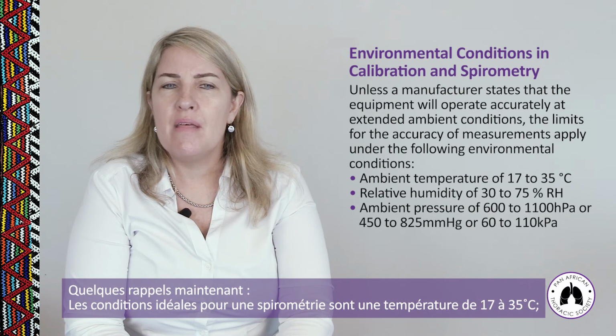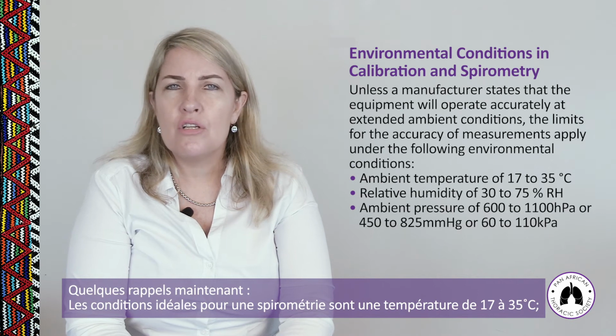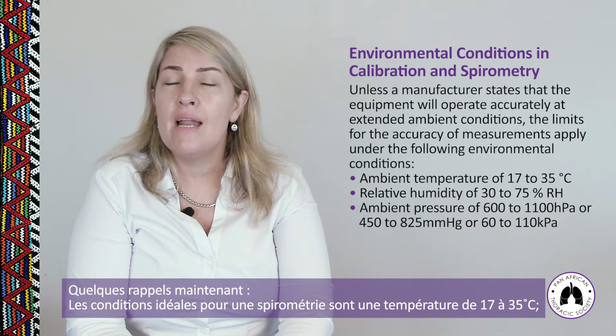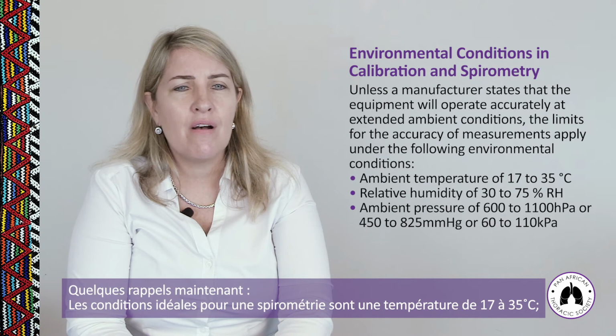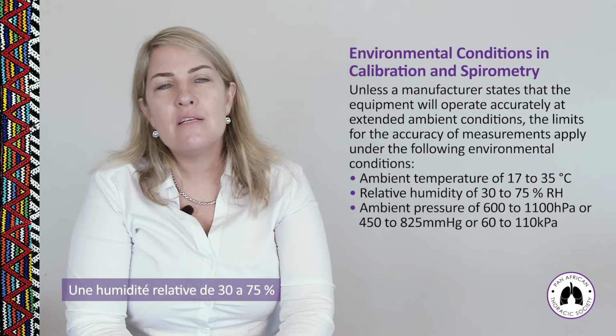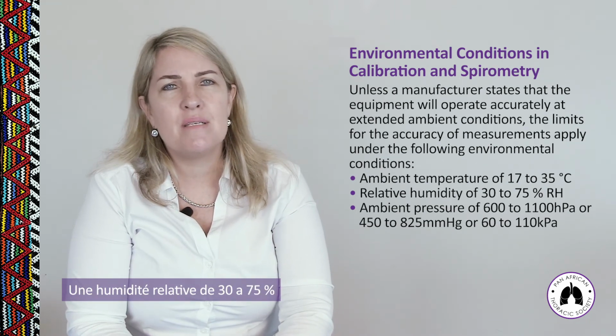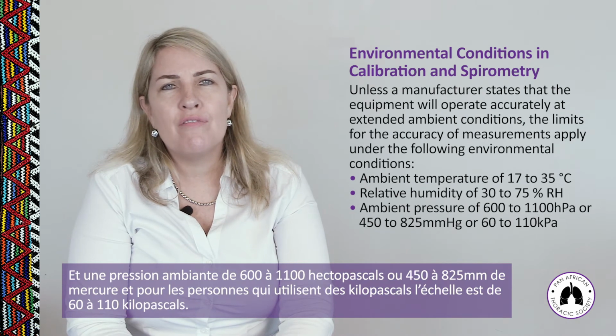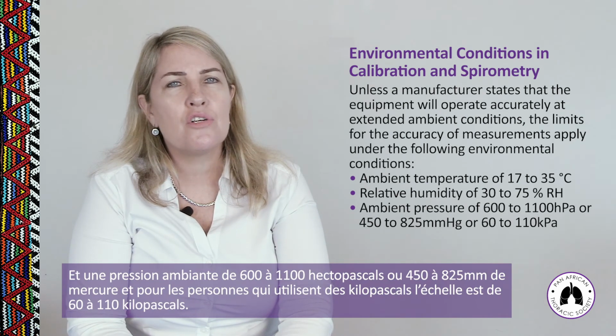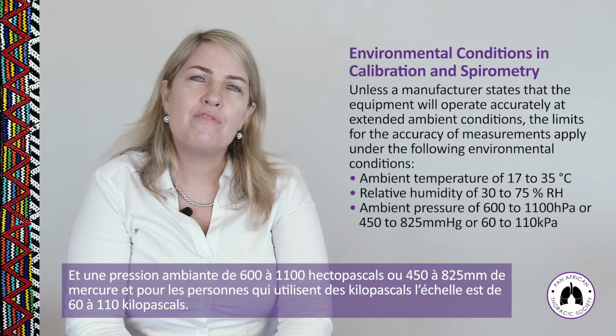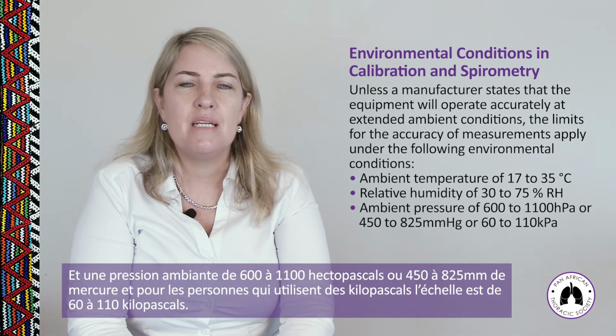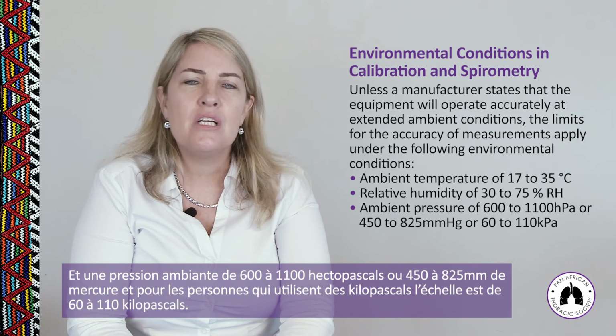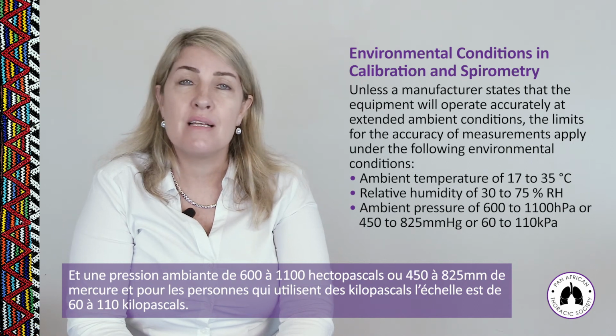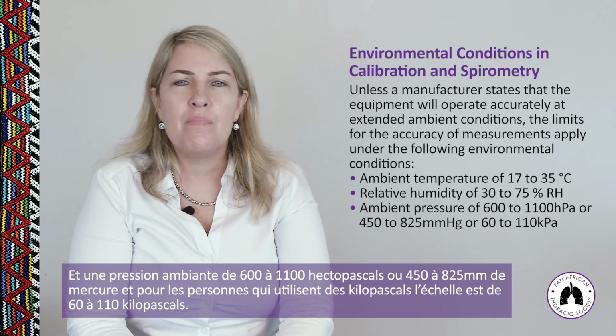So just to recap then, the ideal ambient conditions for spirometry are an ambient temperature of 17 to 35 degrees Celsius, a relative humidity of 30 to 75%, and an ambient pressure of 600 to 1,100 hectopascals or 450 to 825 millimeters of mercury. And then occasionally some people do measure in kilopascals, and your ranges allowed would be 60 to 110 kilopascals.